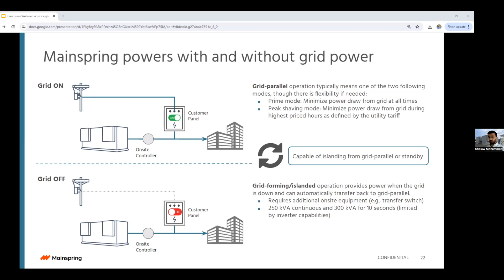Now, in case of a utility outage, we can also run it in island mode. So by adding a couple of other pieces of equipment on site, we'll be able to determine an outage automatically, open the main breaker, change the mode of operation within the LGen, and start establishing voltage and frequency for the site. And because of our load tracking capability, ramping up and ramping down, we're able to meet the required load on site without any issues or third-party support.